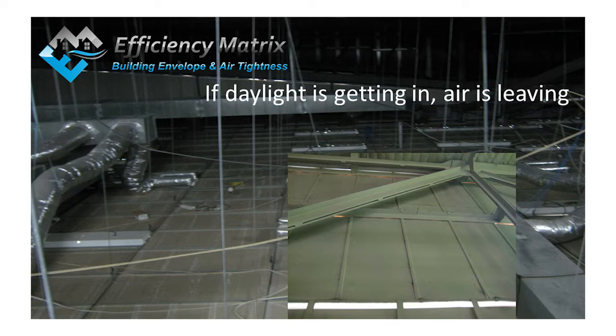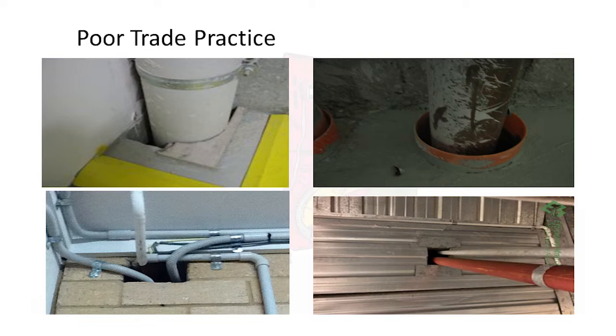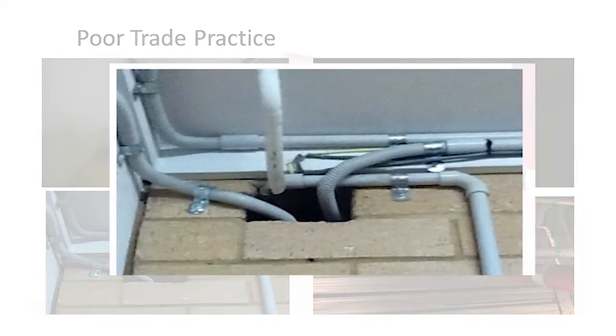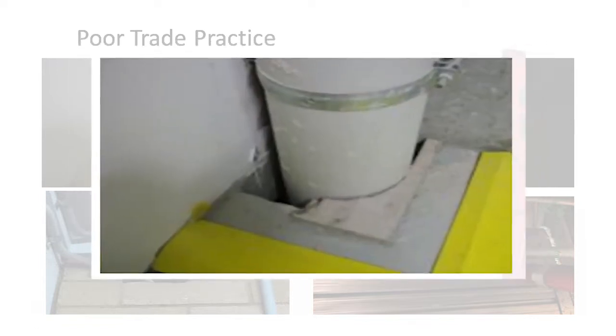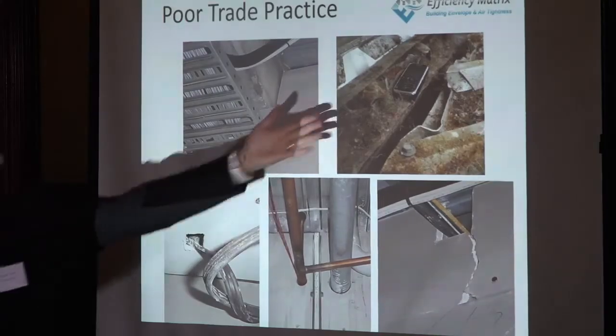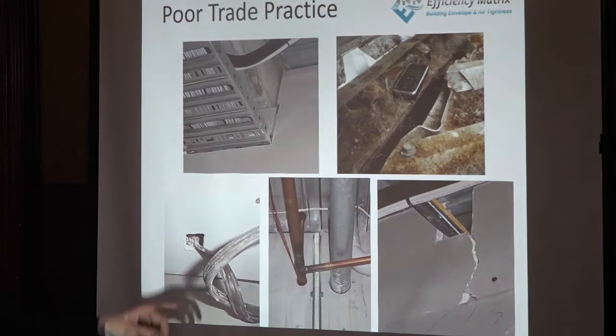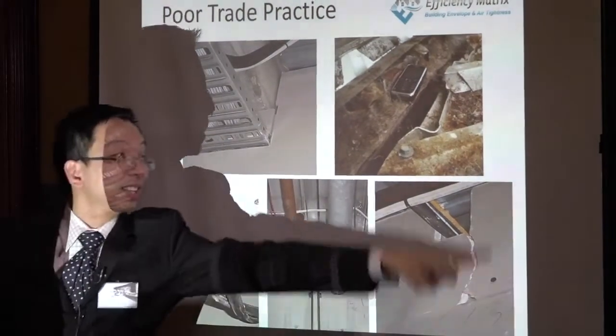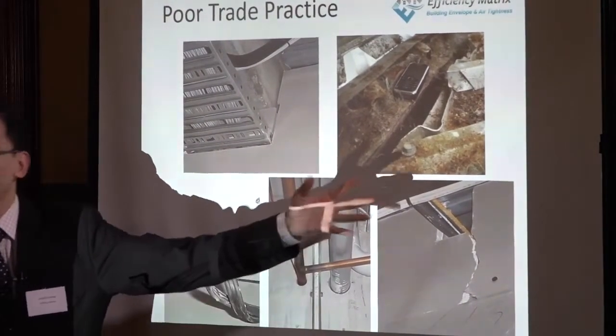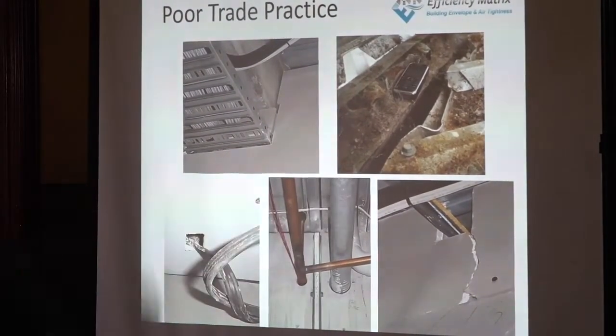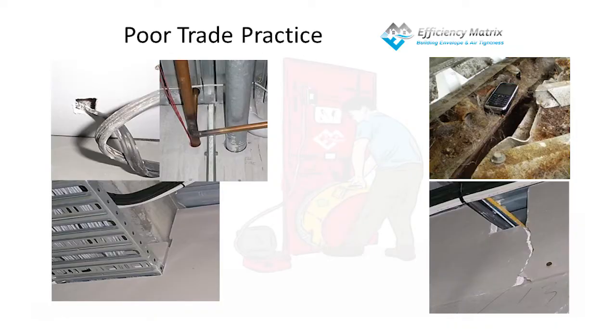Trades, when they need a penetration, take out the whole block. This one is half-hearted but not quite there. Likewise they try to patch up to reduce leakage — at least they're not taking the whole plasterboard out — but you still have plenty of air leakage around those details.